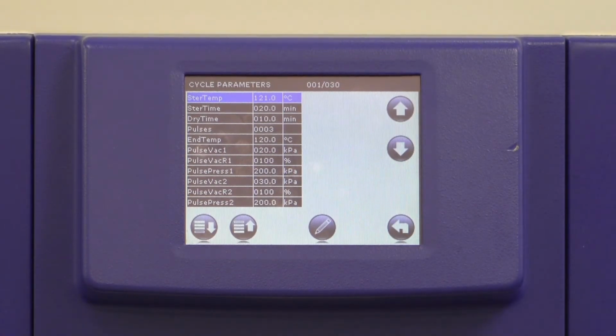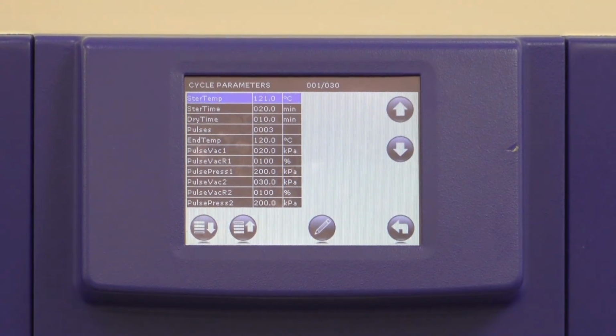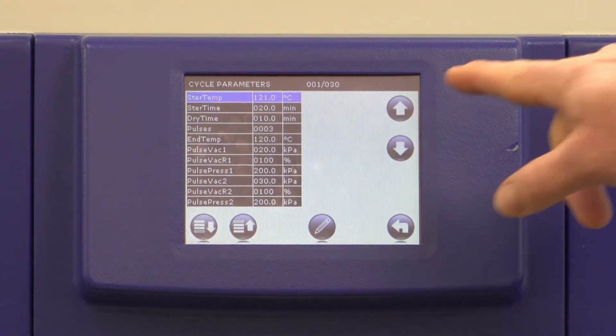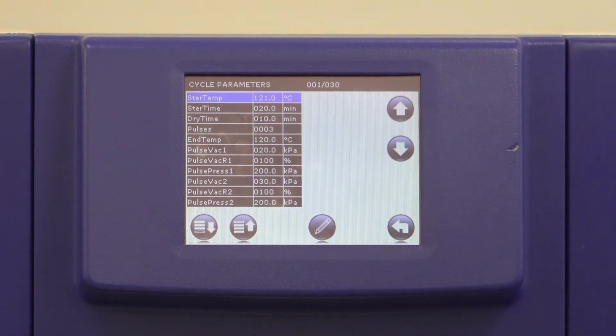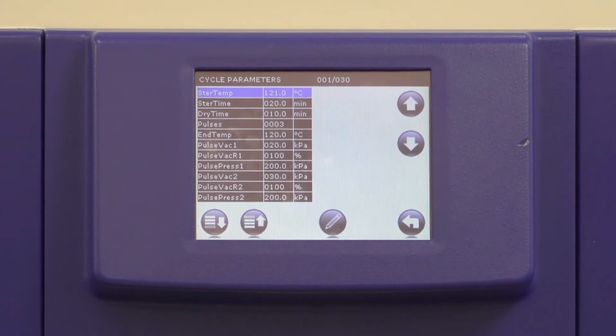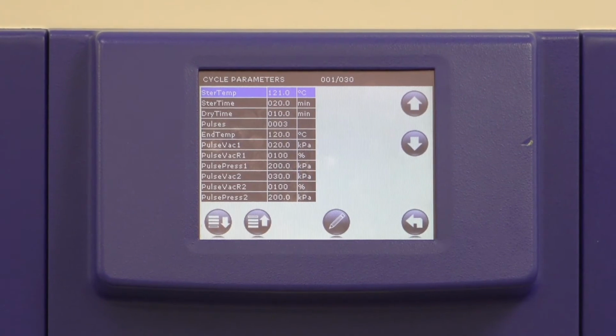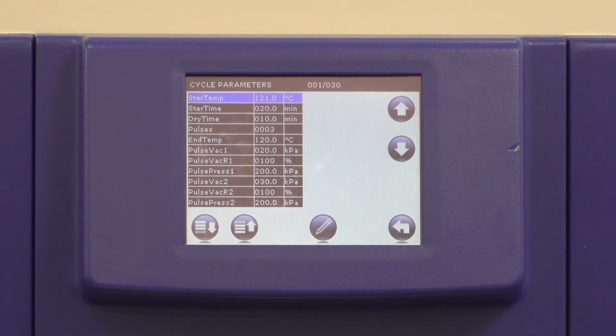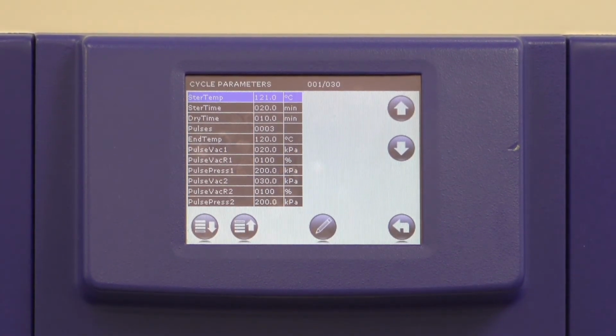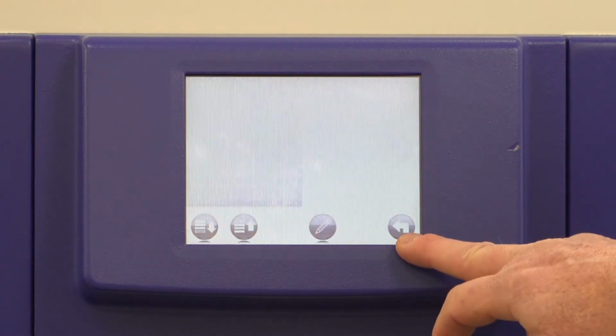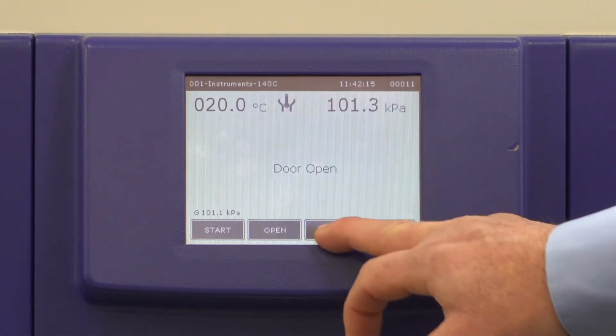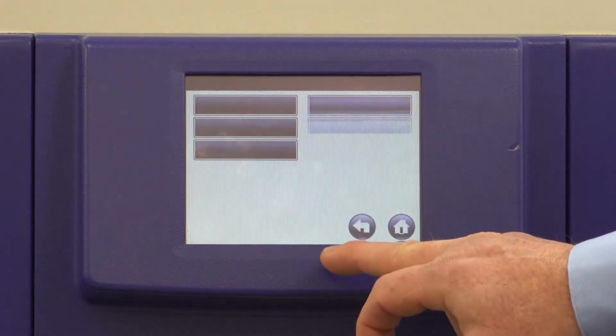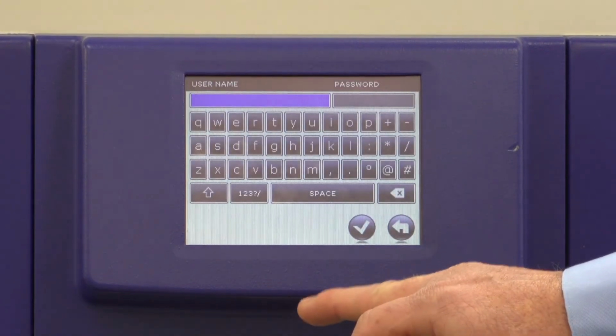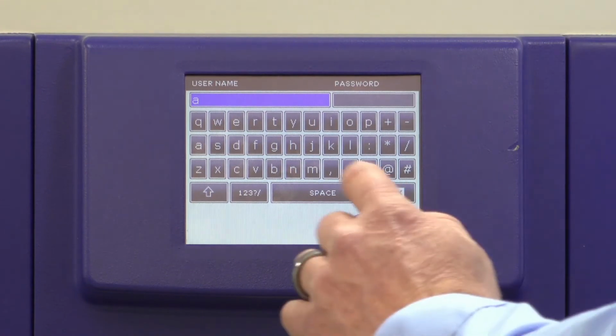With other access codes, I entered an admin code there. I have access, as you can see at the top right here, I have access to 30 parameters that I can change with that administration code. We can lock that down to where we have just a user password. That user may only be able to access 3 or 4 different parameters. Or they may be able to start a cycle, but they would not be able to change any of the parameters. So those are all, I can go to my user menu as well and go to my user list. I have to enter a password again.